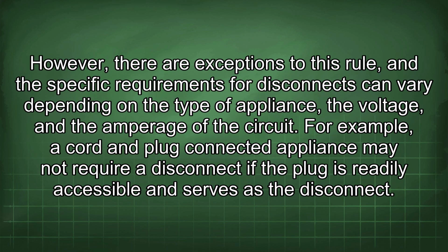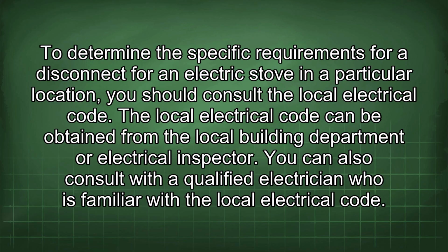However, there are exceptions to this rule, and the specific requirements for disconnects can vary depending on the type of appliance, the voltage, and the amperage of the circuit. For example, a cord and plug connected appliance may not require a disconnect if the plug is readily accessible and serves as the disconnect. To determine the specific requirements for a disconnect for an electric stove in a particular location, you should consult the local electrical code.